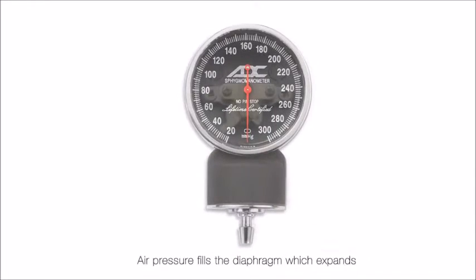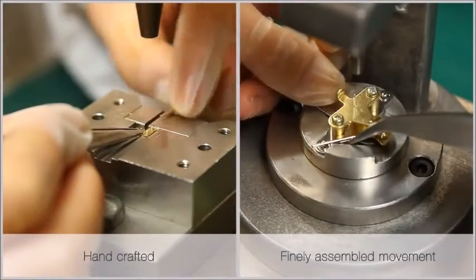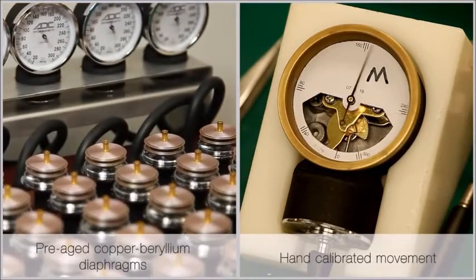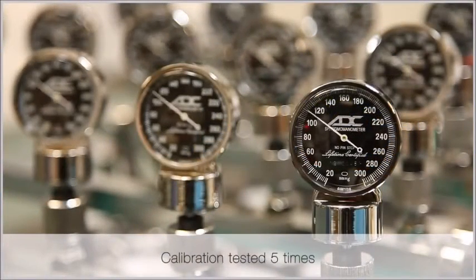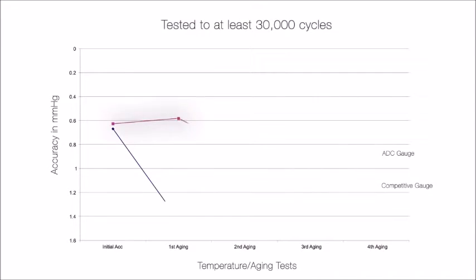Aneroid manometers use a watch-like movement to measure the air pressure applied to the cuff. ADC manometers were exclusively engineered for us by Nissei, Japan's leading and oldest manufacturer of pressure-sensitive instruments. ADC manometers exceed industry accuracy requirements by up to 66% and are built to endure.